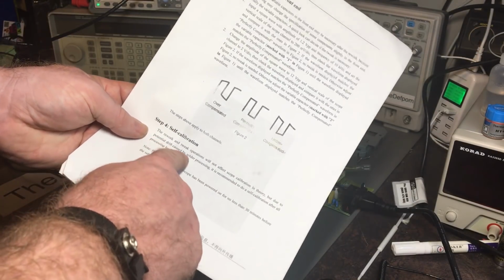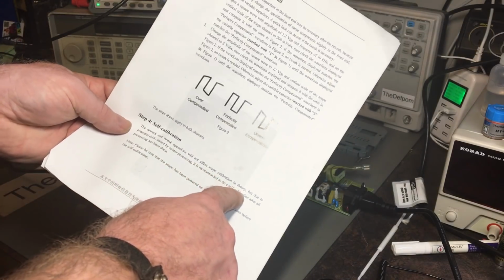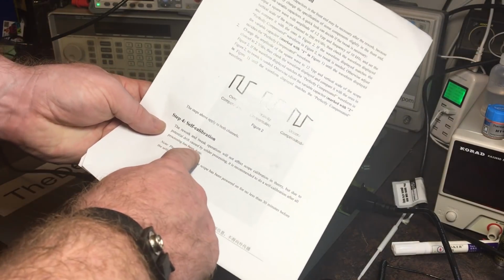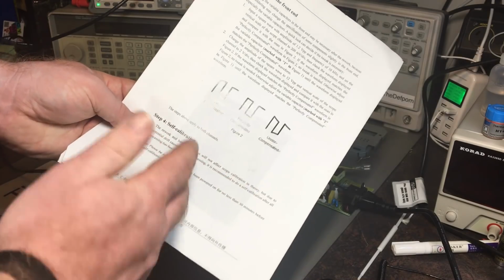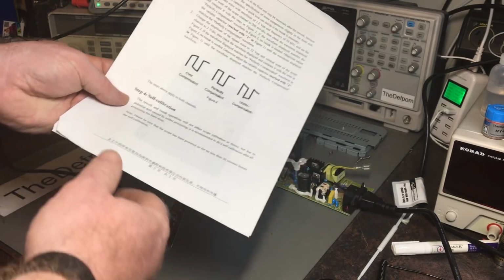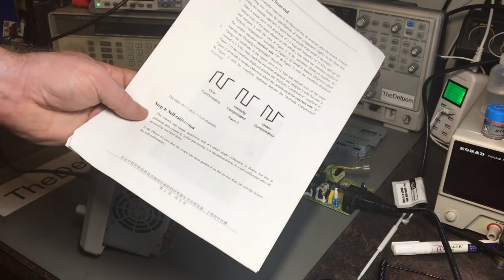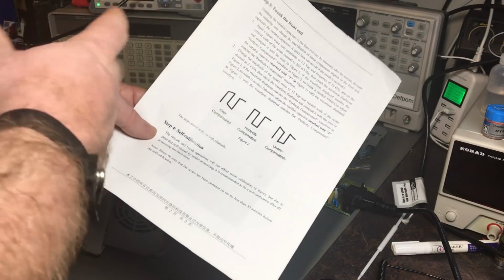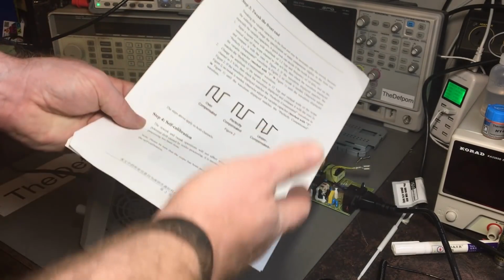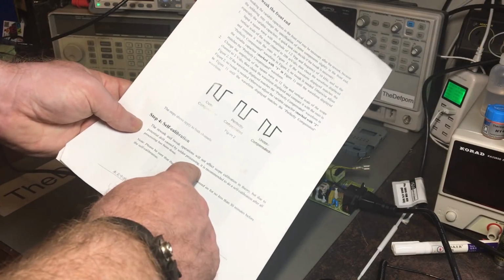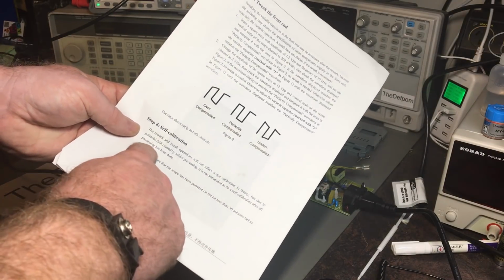Now it says rework and tweak operations will not affect the scope calibration in theory, but due to potential drift caused by solder processing, as in the residue left over, flux, IPA, that kind of thing, right? It may have actually removed some flux that was left on the board, possibly. May have left it cleaner than it was when we started. So it is recommended to do a self-calibration after all processing has been done.